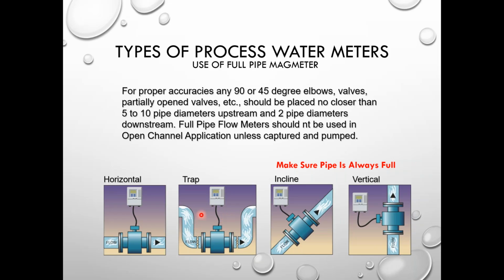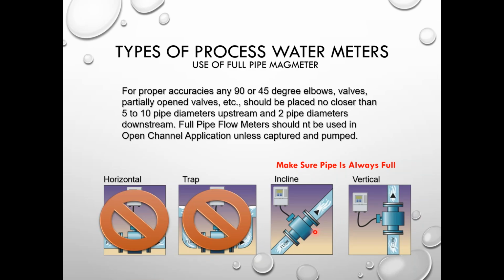I would not recommend using a P-trap style system, especially if you have a facility where there's a possibility of plugging, as it could make it very difficult for them to maintain. Also, I would not recommend using mag meters in a horizontal run, because you've got a partially full pipe on a typical horizontal gravity line. You could do it on inclines. You just want to make sure there's some sort of a valve or check valve here that keeps the pipe full. Most mag flow meters will have some sort of empty pipe detection alarm, and it'll wreak havoc on the system when that sensor is just sitting in air.